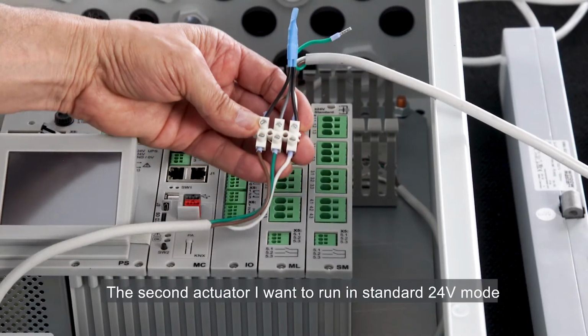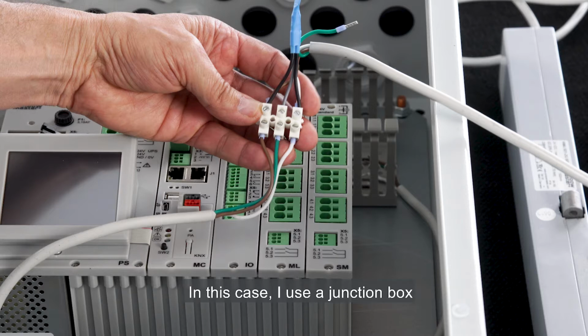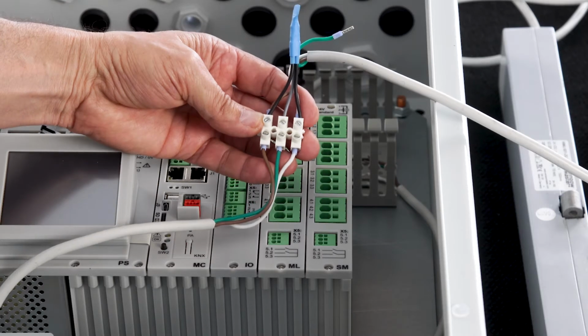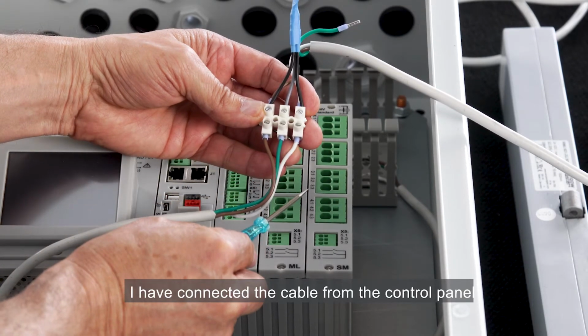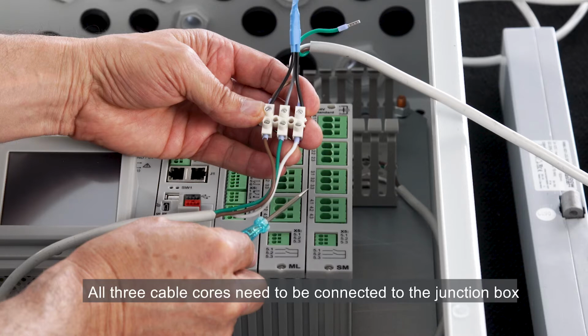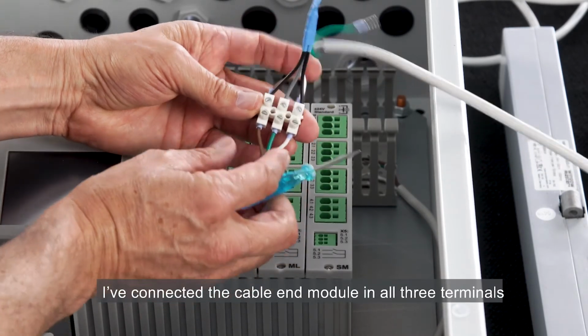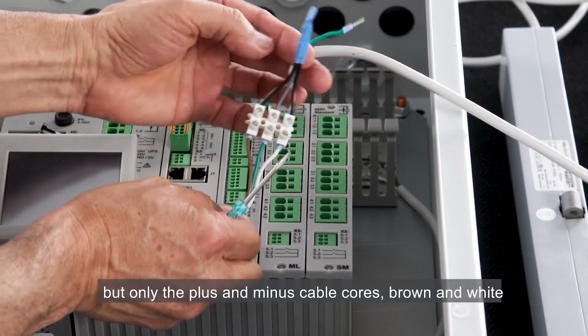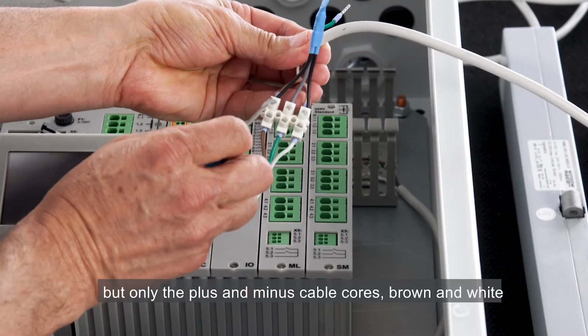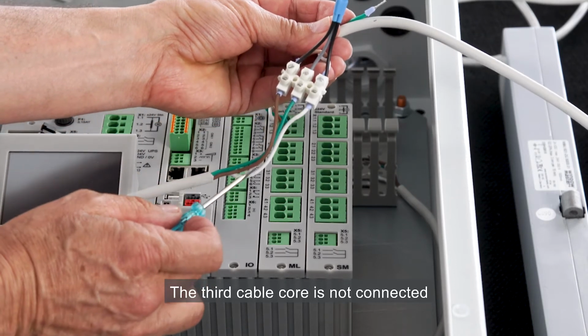The second actuator I want to run in standard 24-volt mode. In this case, I use a junction box. On this side of the junction box, I've connected the cable from the control panel. All 3 cable cores need to be connected to the junction box. On the other side, I've connected the cable end module in all 3 terminals. I've also connected the cable from the actuator, but only the plus and minus cable cores, brown and white. The third cable core is not connected.